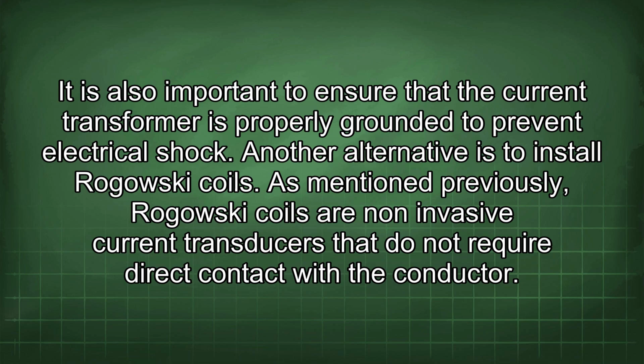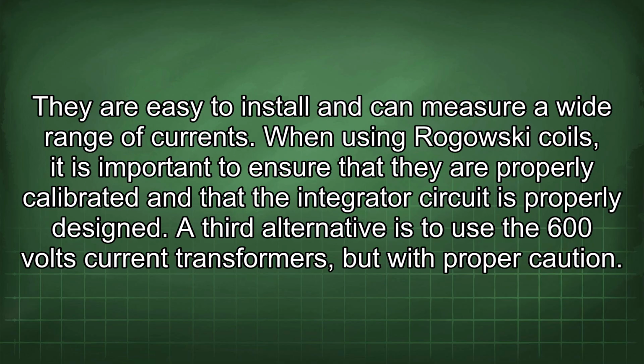As mentioned previously, Rogowski coils are non-invasive current transducers that do not require direct contact with the conductor. They are easy to install and can measure a wide range of currents. When using Rogowski coils, it is important to ensure that they are properly calibrated and that the integrator circuit is properly designed. A third alternative is to use the 600 volts current transformers, but with proper caution.